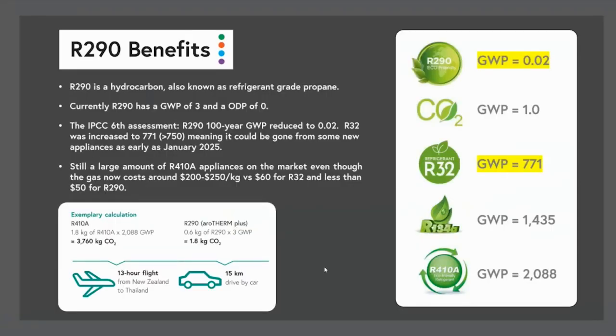Let's have a look at R290. Where does this sit and what's the current situation? As I mentioned, R290 is a hydrocarbon. It's also known as refrigerant grade propane. It currently has a GWP of 3, that's global warming potential of 3. And it has an ozone depletion potential, that's ODP, of 0. So it doesn't affect the ozone at all. Neither do most of the refrigerants on this list.